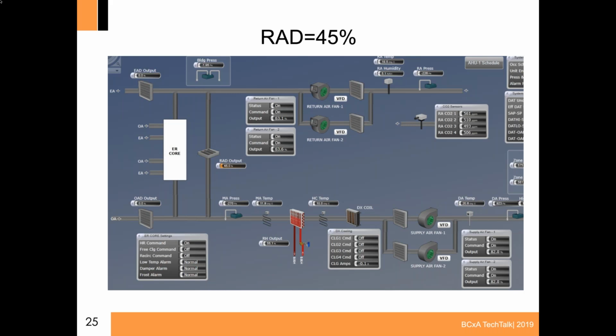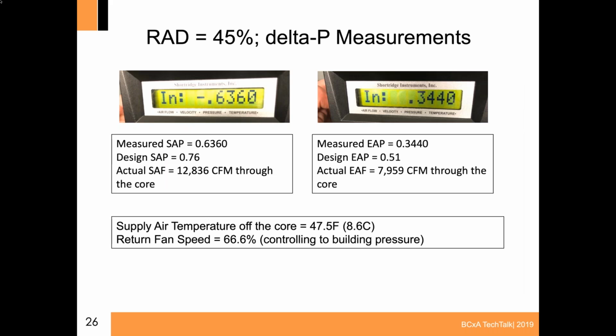At 45%, we can see now our mixed air temperature actually jumps quite significantly. We're just under 12 degrees Celsius, and our return fans came up slightly. So what was the impact of this one? We have now gone to just under 13,000 on the core and just under 8,000 on the exhaust flow. So basically all we've done at this point is we've adjusted the return air damper. Now we wanted to play a little bit with the return fan, start bringing it back up to where it was and see what that will affect.